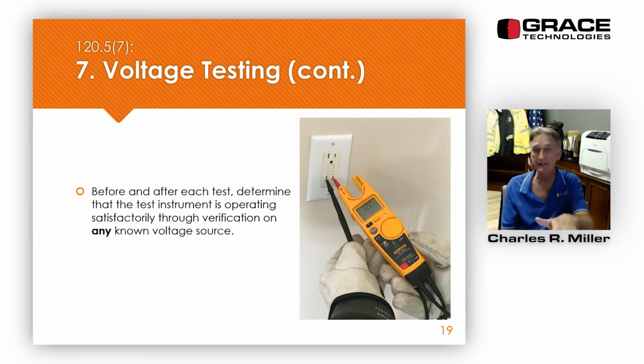Now, it used to say, it didn't change in this edition, it changed in 1 or 2 editions back. It used to say we verify on a known voltage source, but now it says any known voltage source. So you could, and it doesn't have to be the same voltage. So maybe you're going to be disconnecting power to a 480 volt 3-phase motor. We can check it on a 120 volt source. It just says any known voltage source.